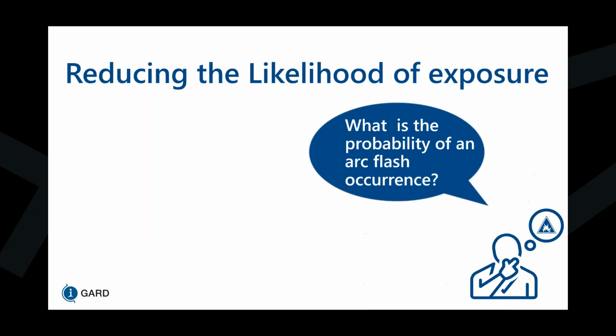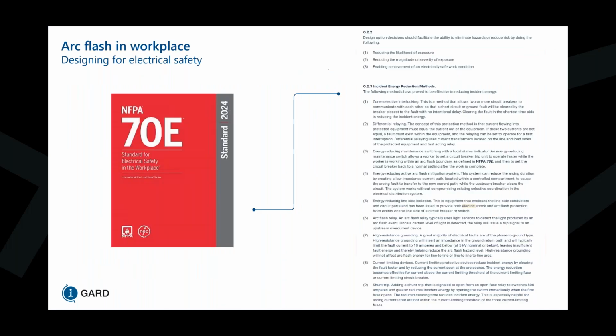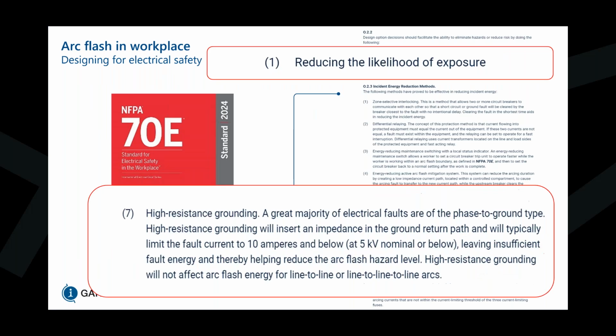Now, when it comes to reducing the likelihood of exposure, or reducing the probability of an arc flash occurrence, we can look at high resistance grounding, which is one of the only incident energy reduction methods of the 9 listed that is reducing the likelihood of exposure. All the other incident energy reduction methods listed are acting after the fact that the arc is already in the system, and it's looking to reduce the magnitude. So when we place that impedance in the ground return path and limit fault current to 10 amps or less on a system that's 5 kV or less, we leave insufficient fault energy and thereby help reduce arc flash hazard levels.